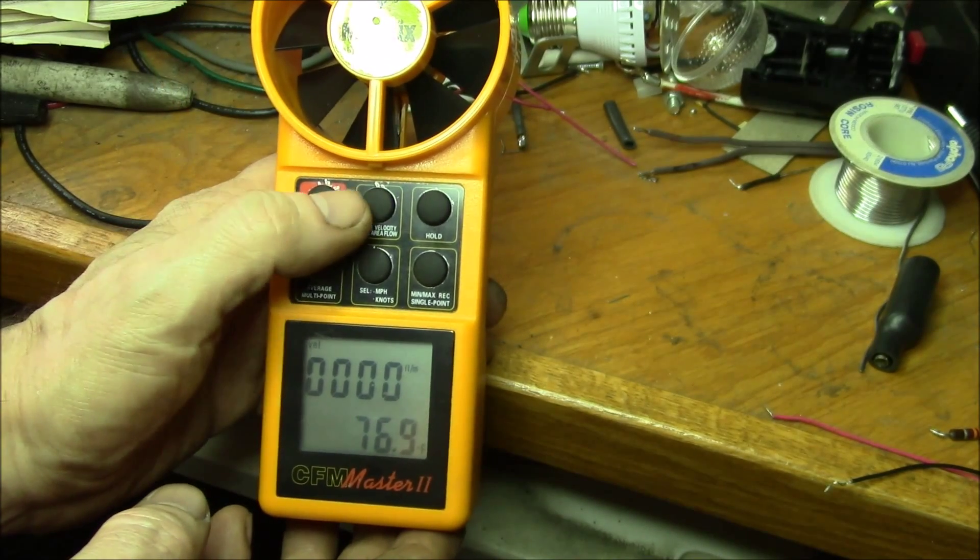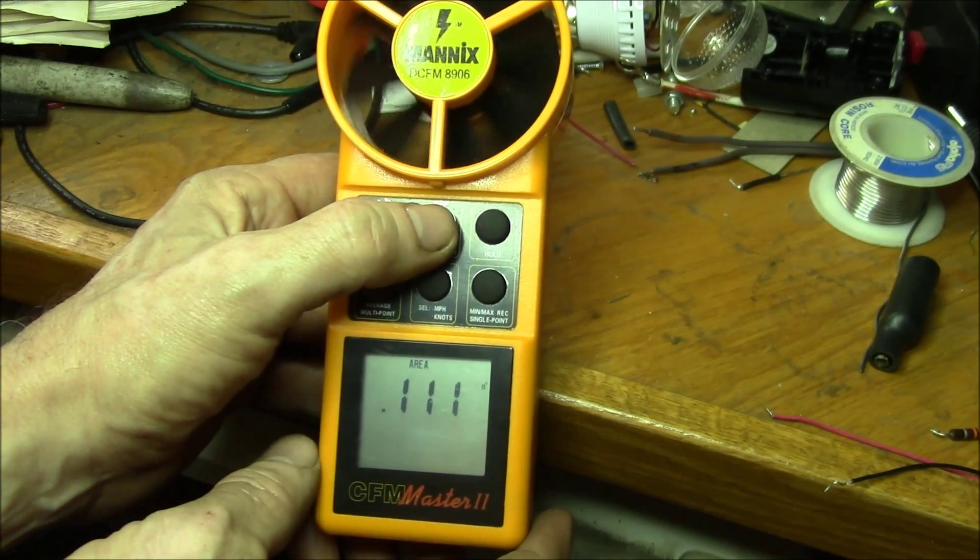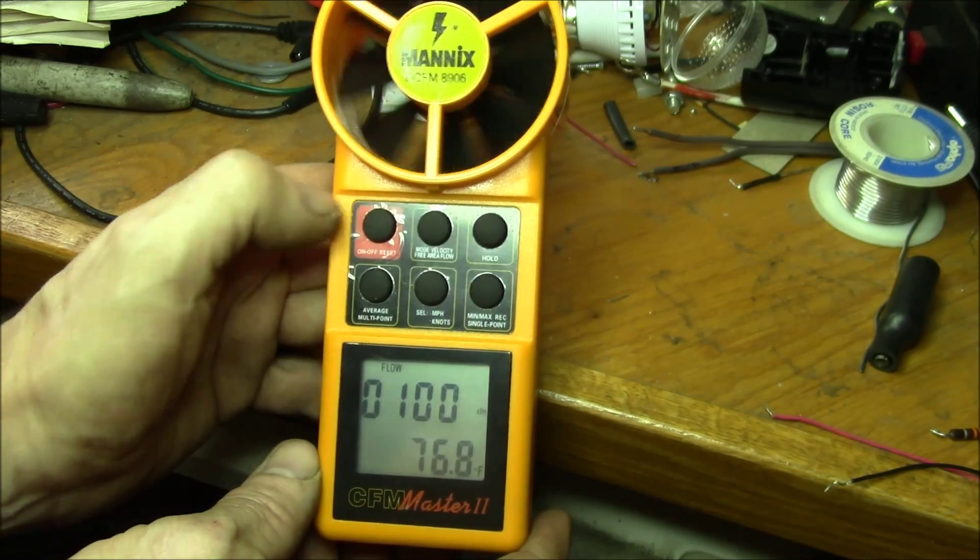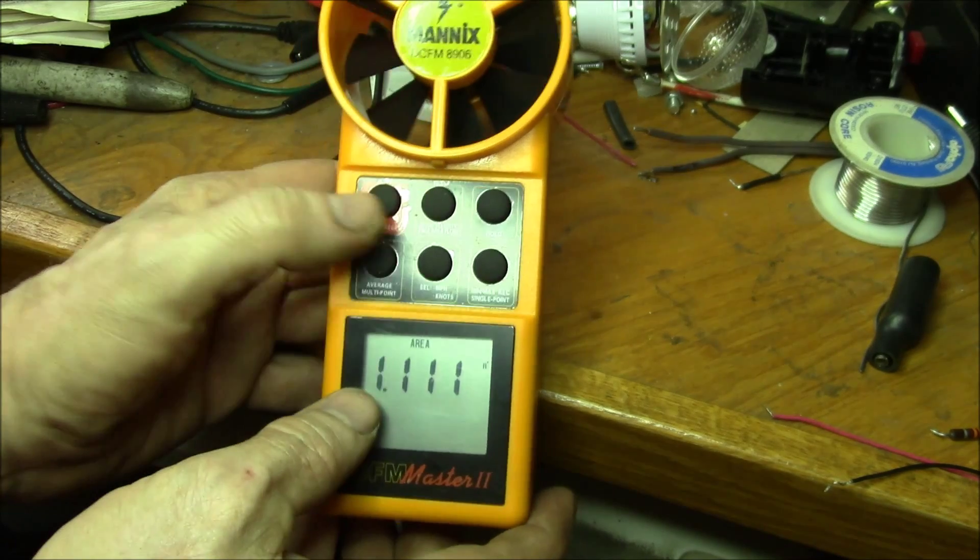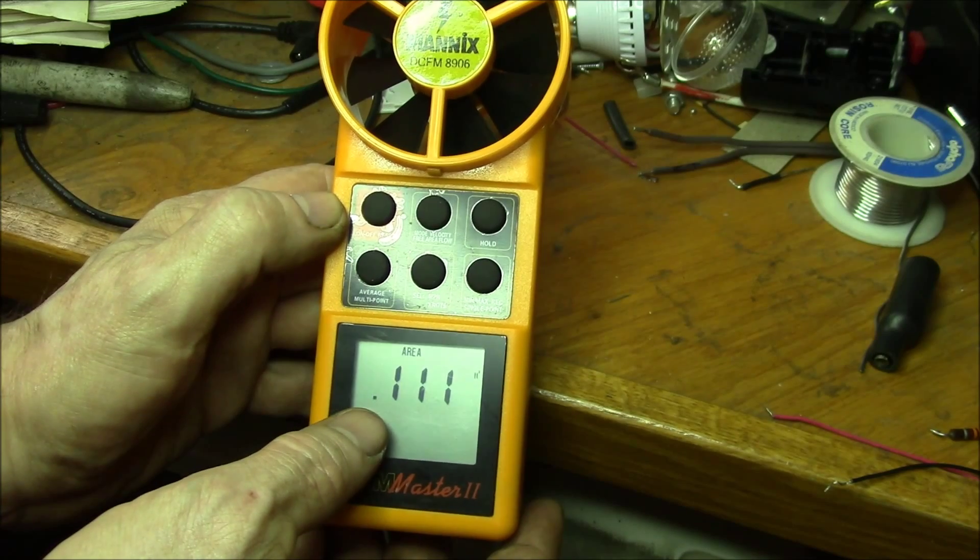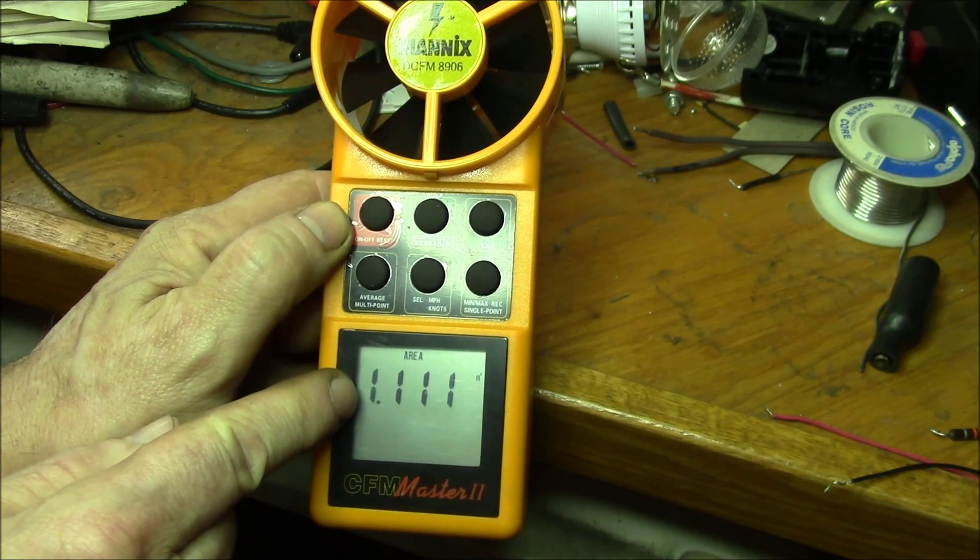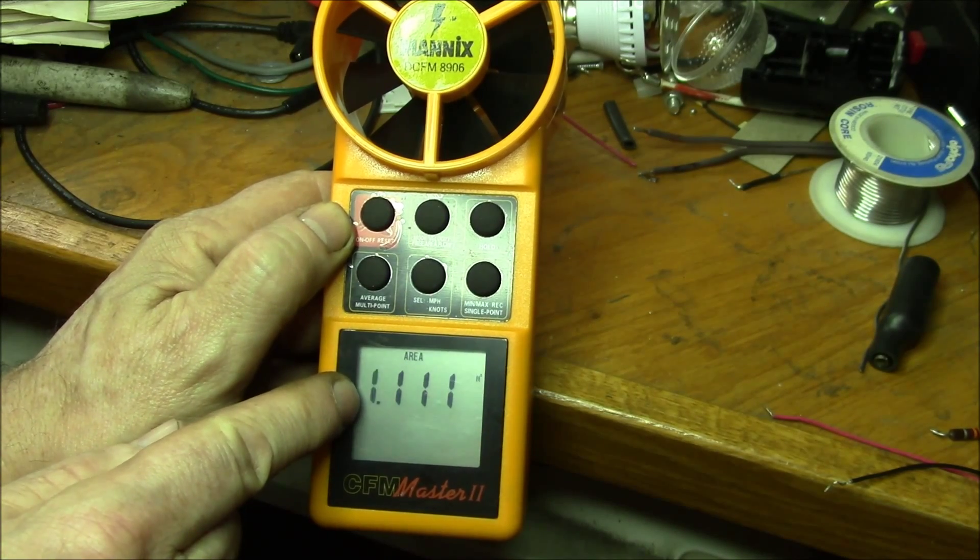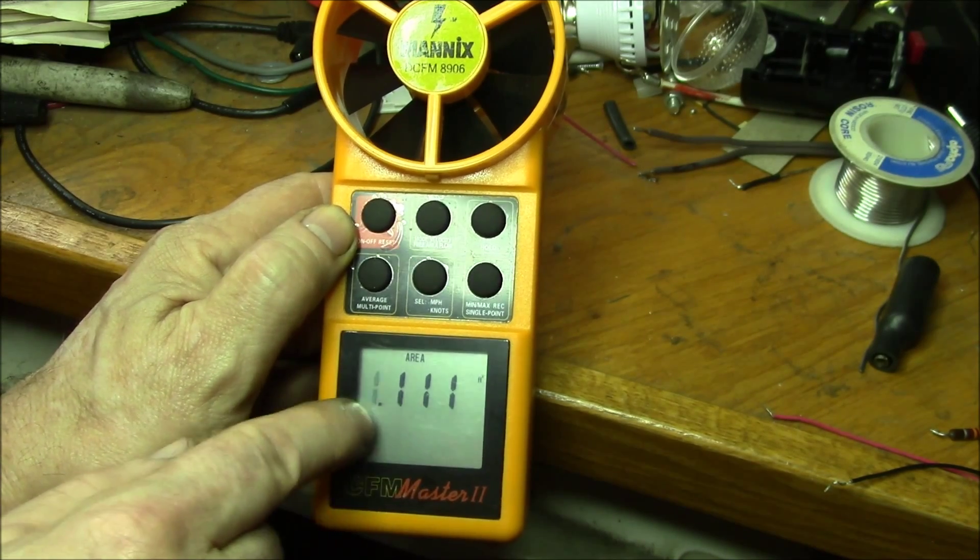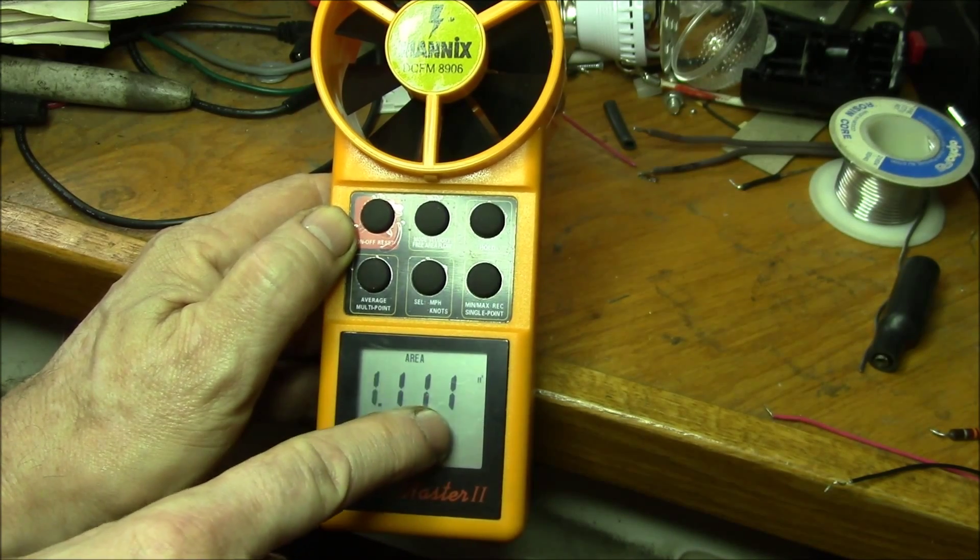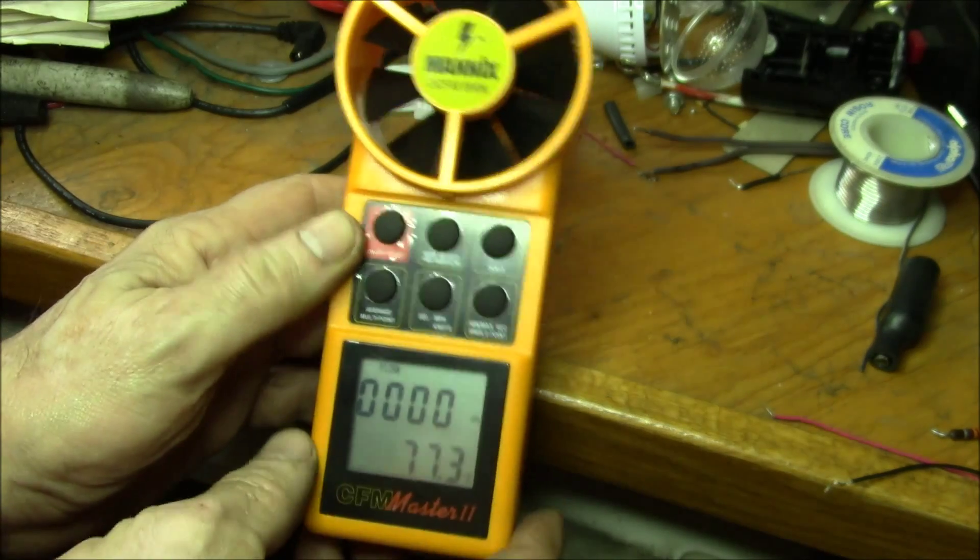This is what they use for balancing forced hot air heating systems. You can either work in cubic feet. The fancier meters will actually have this setting where you can select your duct size, like a four inch duct or six inch duct. With this meter you've got to look up in a table what the equivalent square feet of a given size duct is, and then you enter the square feet of the duct in here and then it computes the cubic feet per minute.